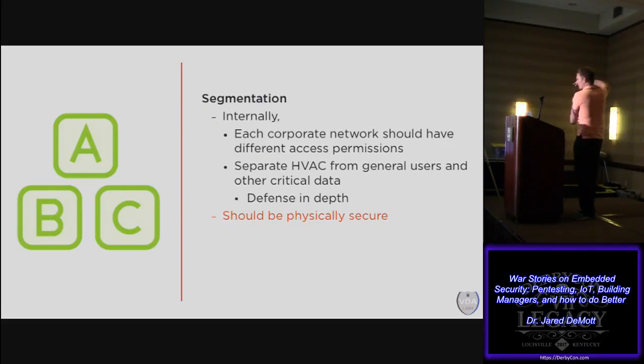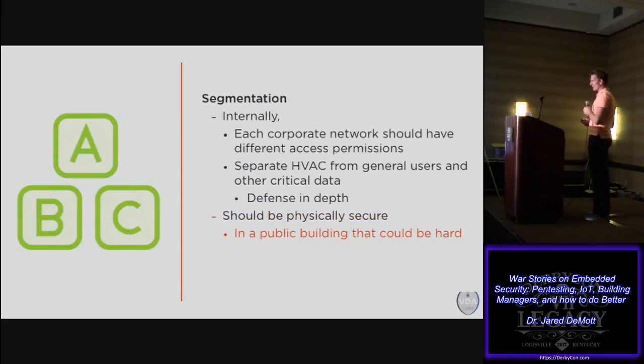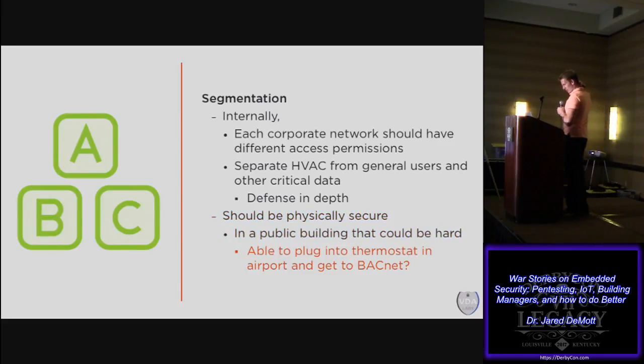Physically secure, too, is important with these kinds of devices. A lot of the SCADA and building systems, a lot of times you can plug into them physically, right? So you walk up to a thermostat in an airport. If you look underneath it, a lot of times there's an Ethernet jack. You can actually plug into that, and you'll be on the building network of the airport. And that's not a good thing.